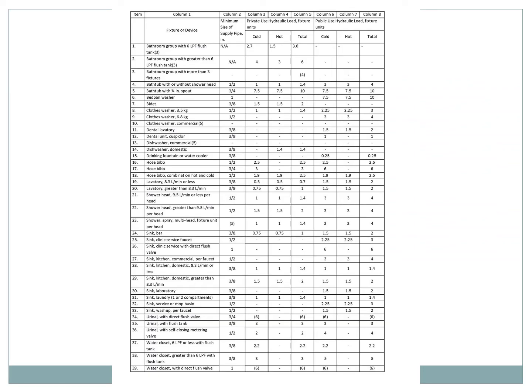Here it is in the table. We'll go with a lavatory basin. You have the same item numbers. There's a lavatory basin that does 8.3 liters per minute or less, and one that does greater than 8.3 liters per minute. I want you to stick with the smallest one — not because it's right or wrong, but to put us all on the same page. Go with the 8.3 liters per minute or less option, and you will see that the minimum supply pipe size is 3/8 inch.